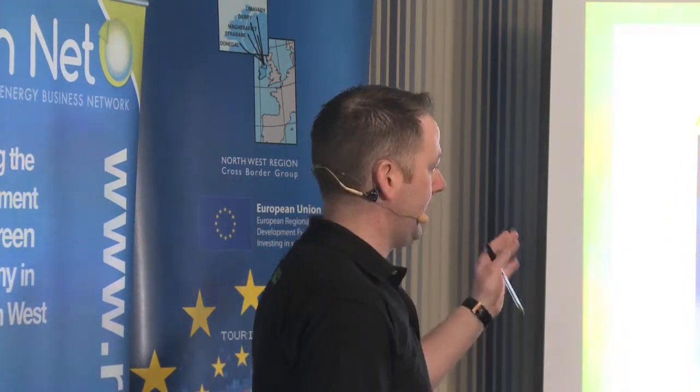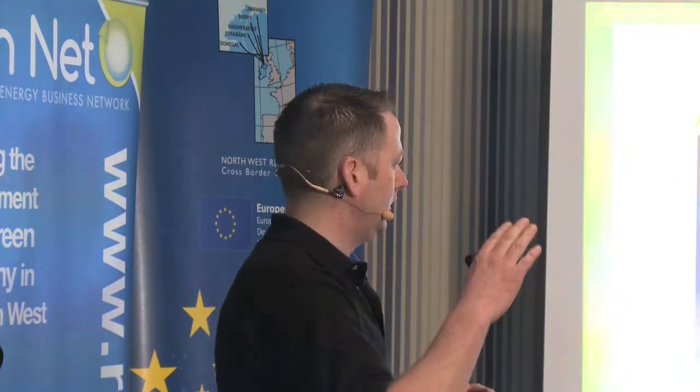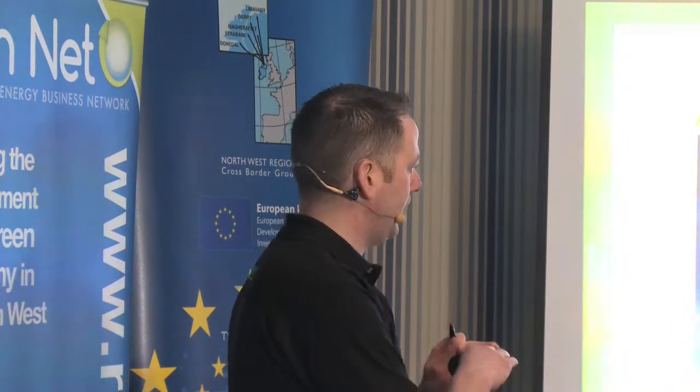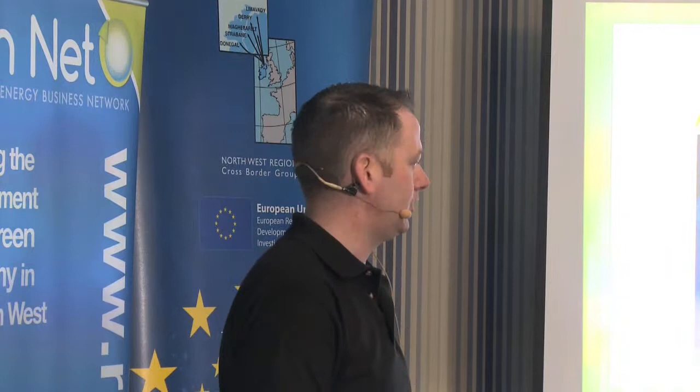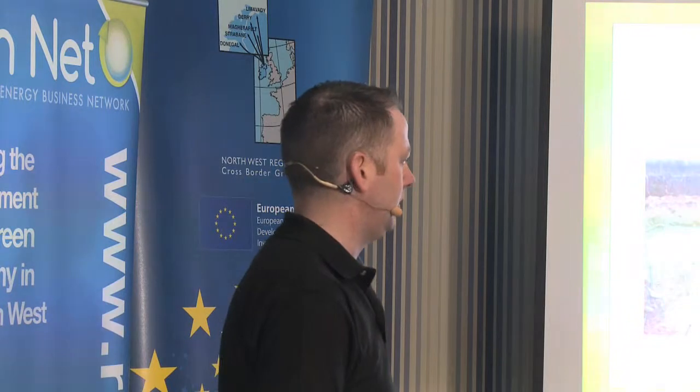The size that I've in my own house and a lot of houses is from a 5 to a 22 kilowatt. So if you only have 1 or 2 bathrooms calling for heat, the heat pump will just slow right down and go very slow. Where if you have all the house calling for heat, it'll ramp up and give more heat to the house. It's like an automatic version of the car. It'll only give what's required at the time. And this both saves on electricity and saves the labour of the heat pump as well, so it prolongs the lifespan of the machine.